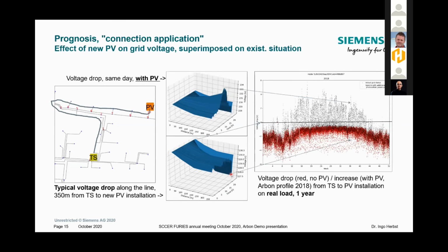Now what's interesting is if you want to compare that to today's situation, you take the year's data at that transformer station, all the time slots, all the data in 15 minute packages over the full year. The red one is what you had before, and the black one that pops up, the positive voltage increase, is what you get on top if you add PV. So that gives you statistical information on what will happen.